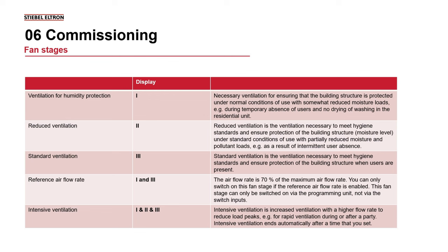Intensive ventilation can be selected on fan speed 1, 2 or 3. This is our purge operation. Intensive ventilation is increased ventilation with a higher flow rate to reduce load peaks. For example, rapid ventilation during or after a party. Intensive ventilation ends automatically after the time that you have set. This can be programmed on the controller, ranging from 15 minutes to 90 minutes.